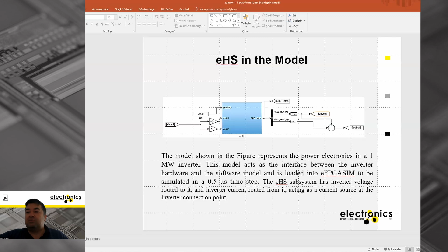The computation subsystem is responsible for numerical calculation. And this is the EHS model of the inverter. The inverter is physical, and we connected it to the simulation environment. This model acts as the interface between the inverter hardware and the software model, and is loaded into eFPGASIM to be simulated for a 0.5 microsecond time step. The EHS subsystem has inverter voltage routed to it and inverter current routed from it, acting as a current source at the inverter connection point.